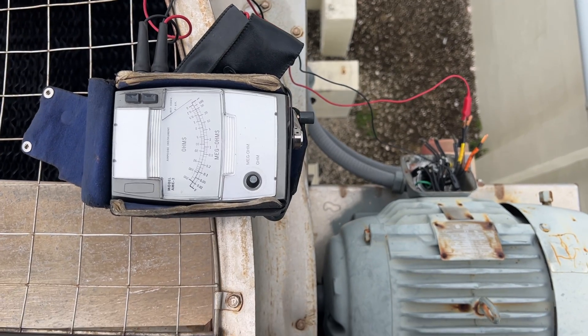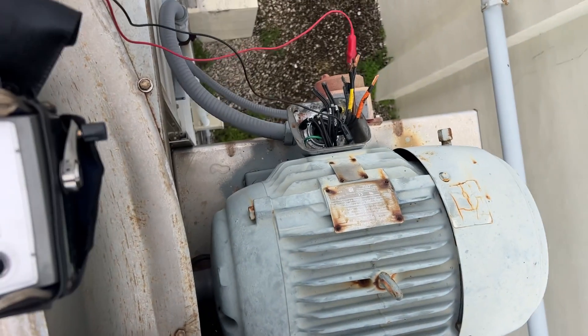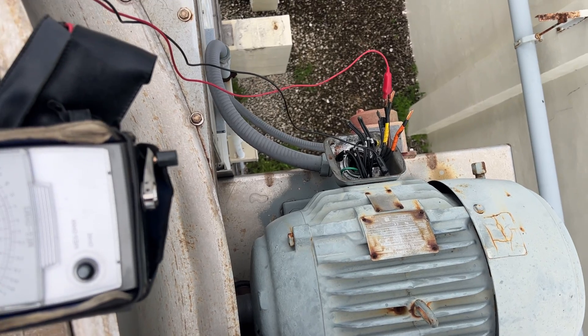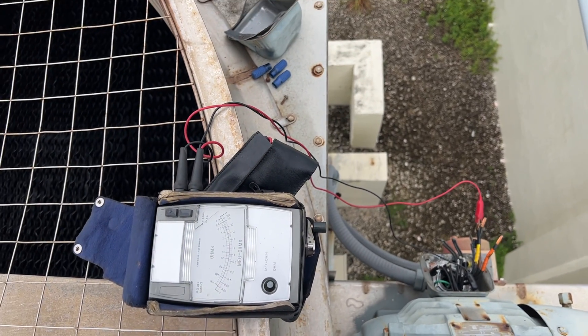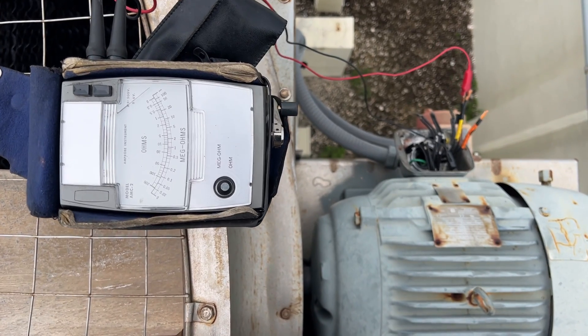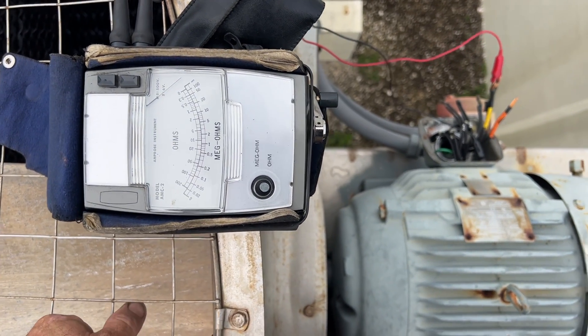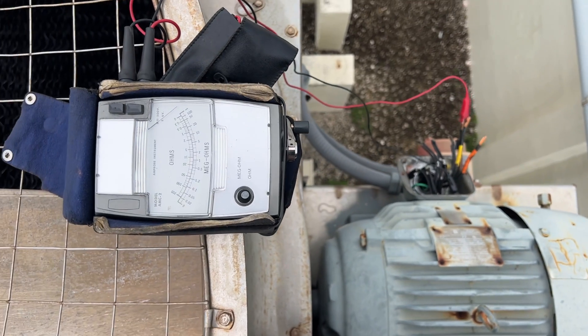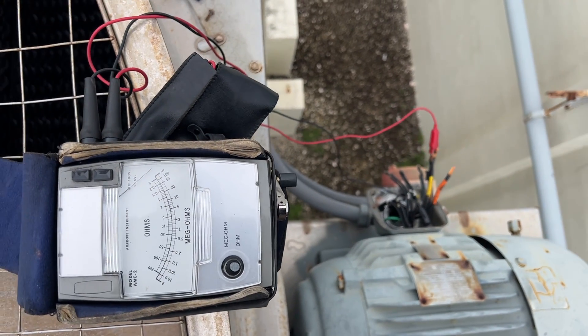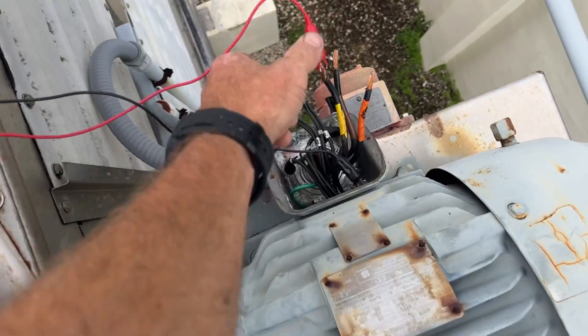We're changing gears here. I decided to come up on top of this tower and check the motor and the wiring, because I had blowing fuses and the disconnect out here. That drive — I get leery when I see blowing fuses and a drive. I want to check the wiring and the motor.